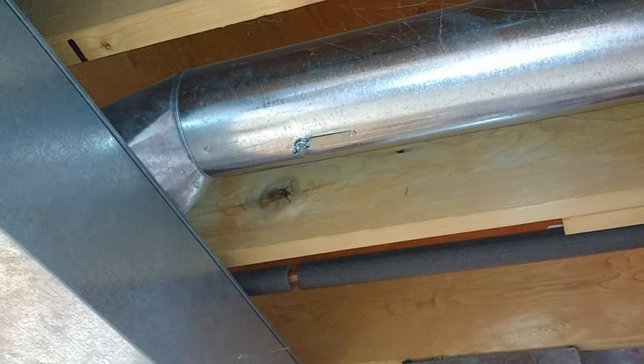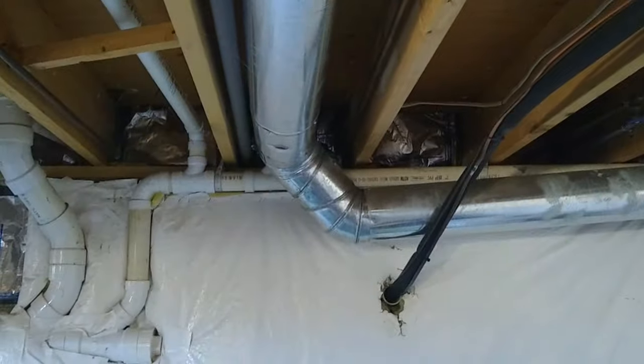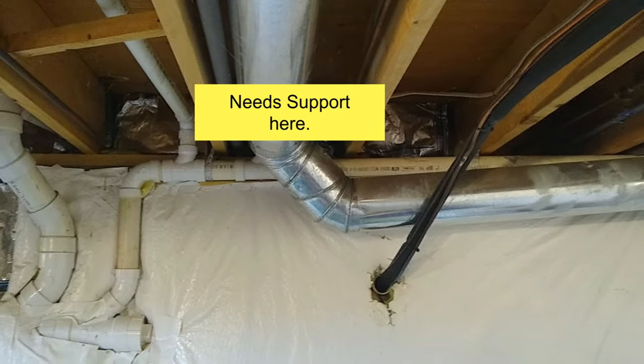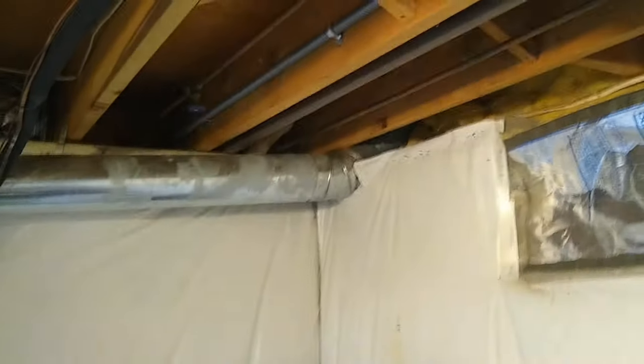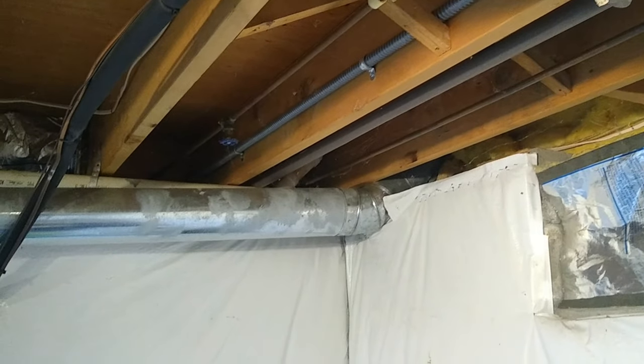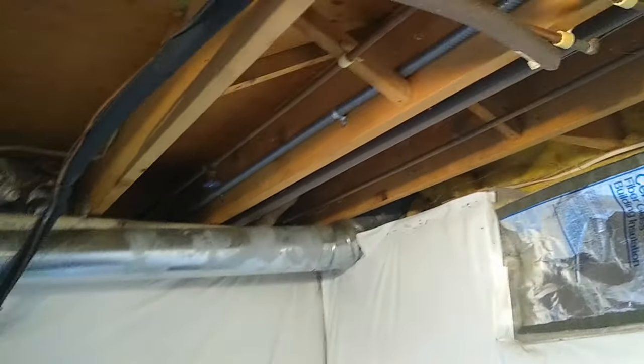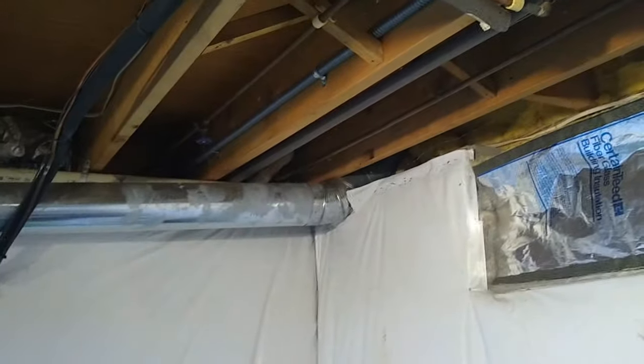The duct is near the end of the main plenum, about as far from the furnace blower as it can get in our house. I put some arrows on it to indicate the direction of the flow. And then it has a drop in it, there, all the way by the back of the house. Then all the way in the far corner it goes up, all the way up to the second floor where it enters the bedroom. Well, it has really wimpy performance. It gets almost no airflow in that room.